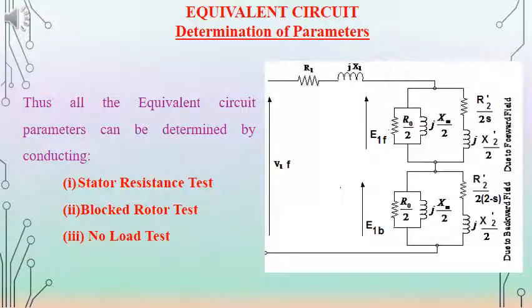The final equivalent circuit is shown in the figure. To find the equivalent circuit parameters of a single phase induction motor, we conduct three tests: blocked rotor test, no load test, and stator resistance test to find R1. In this section, we discussed the equivalent circuit of a single phase induction motor, how to find parameters from different tests, and the double revolving field theory.